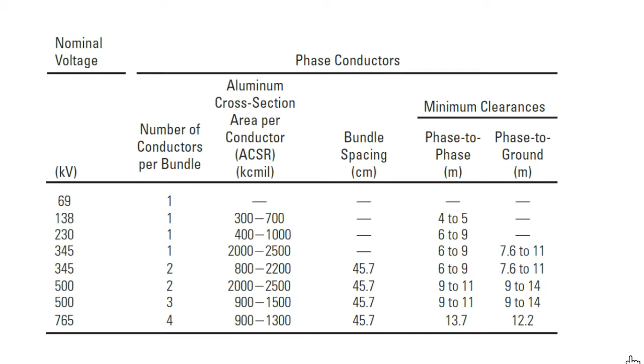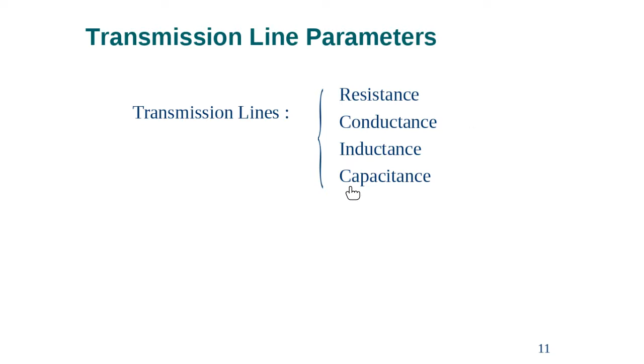All right, the last thing, maybe the last slide here. We have the transmission line parameters: resistance, conductance, inductance, capacitance. And for the resistance, it depends on the area. Once the cross-sectional area is large, as you know, the resistance will be small. And that's why in air conditioners, for example, the wires in your house will be 6 millimeters or 4 millimeters for a 1.5 ton unit. But in the lighting, for example, you will see 1.5 or 2 millimeter, thin wire for the lighting. While for the oven, for example, you see 6 millimeter.